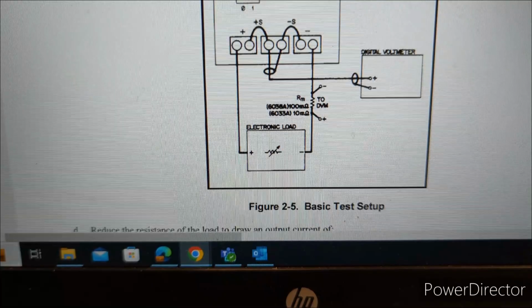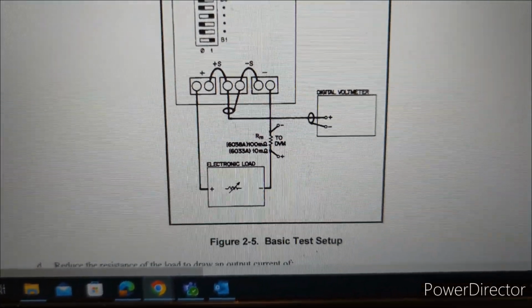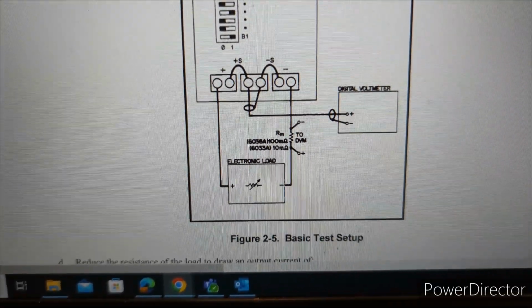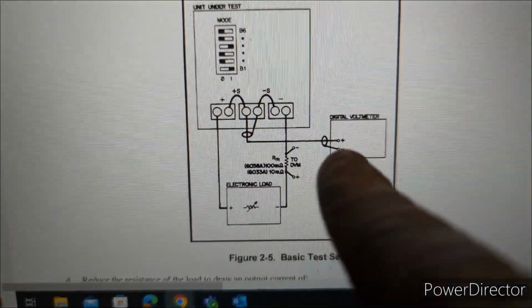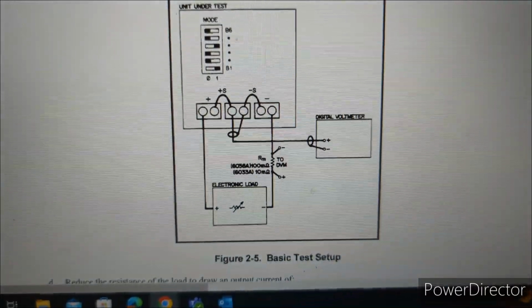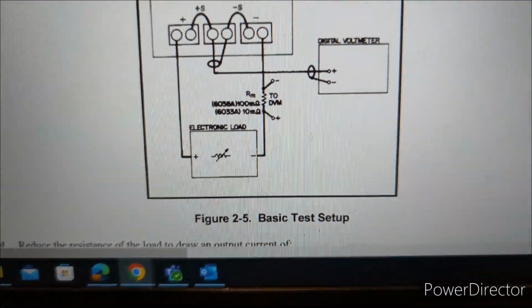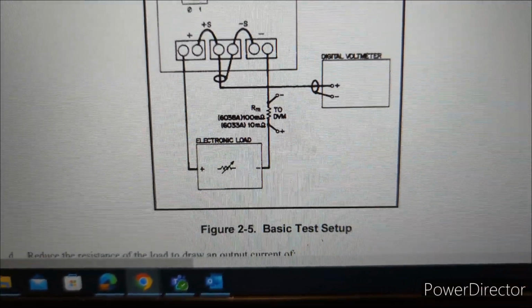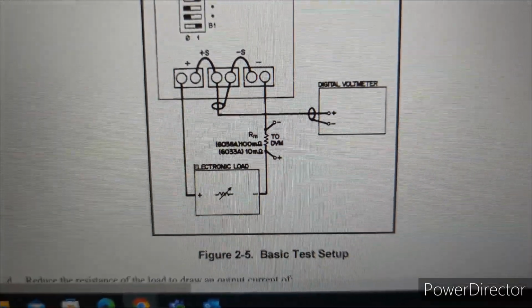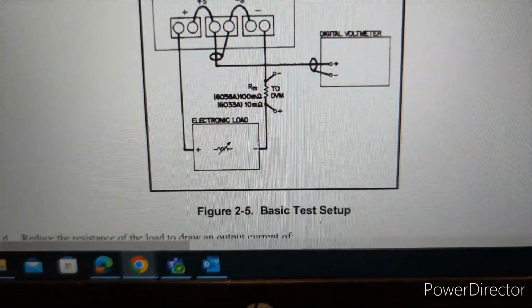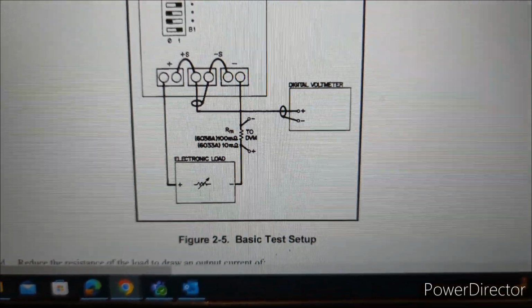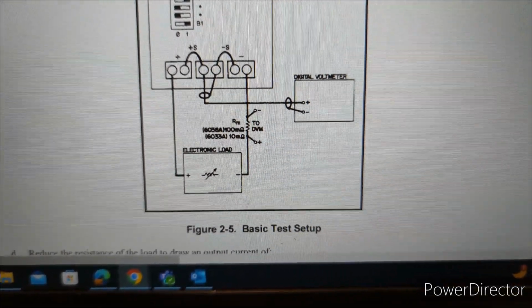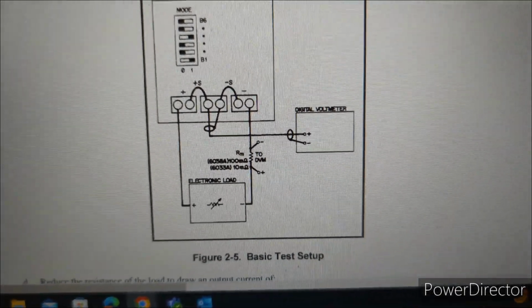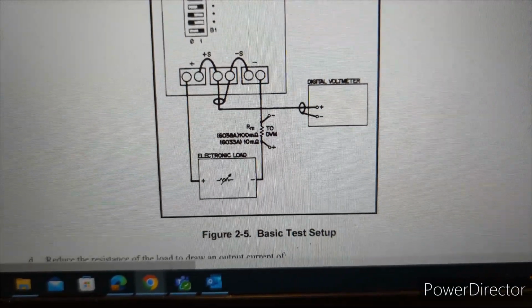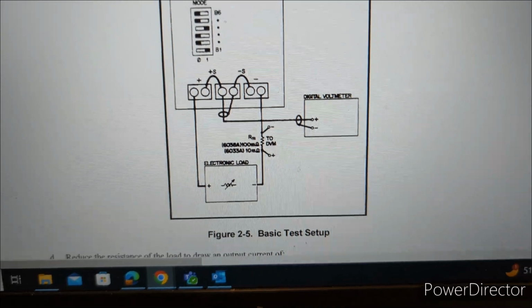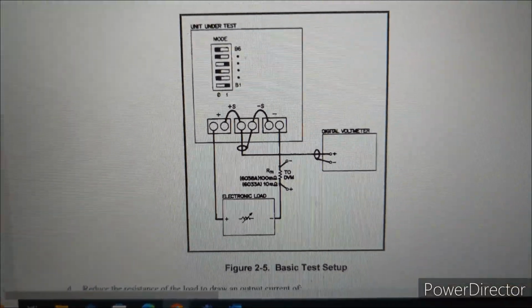test, and this is the setup that it has for the test. So you've got an electronic load on the outputs of the instrument, and then a digital voltmeter is connected to the sense outputs, and what they're signifying here with the circles is actually a coaxial cable. Now they also have what looks like a current monitoring resistor between the negative terminal of the output and the negative terminal of the electronic load, and it says to DVM. So that's kind of confusing me a bit. I don't know if that's monitoring current, if that connects to that digital voltmeter. I'm not really sure what they're getting at here. And if this is obvious to you, please let me know in the comments.